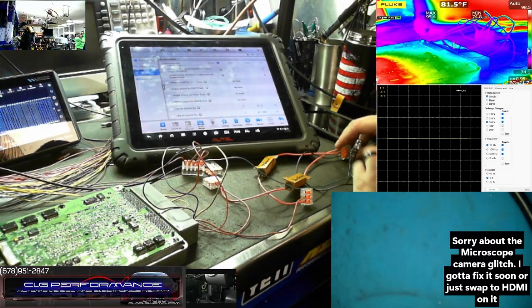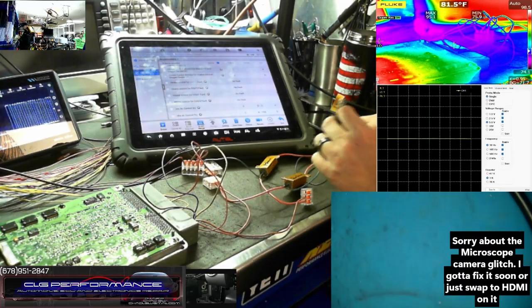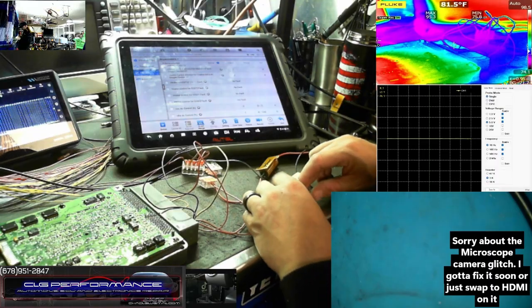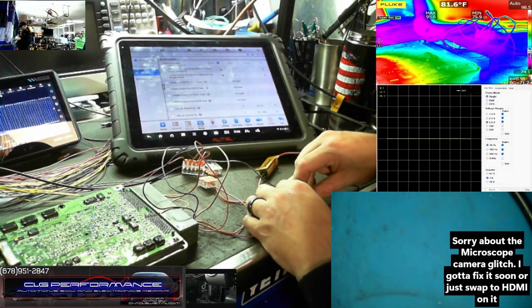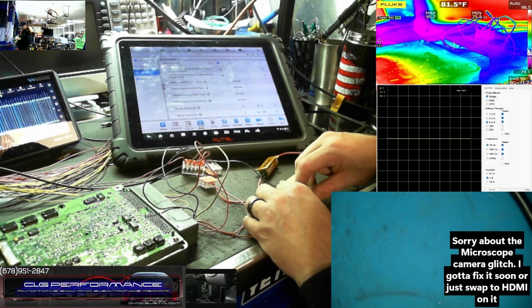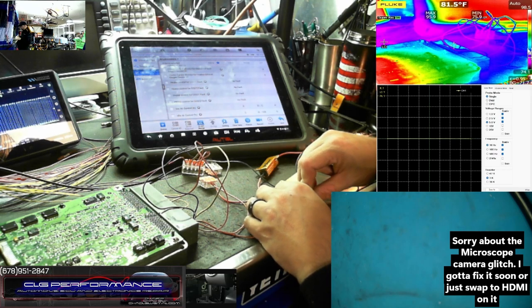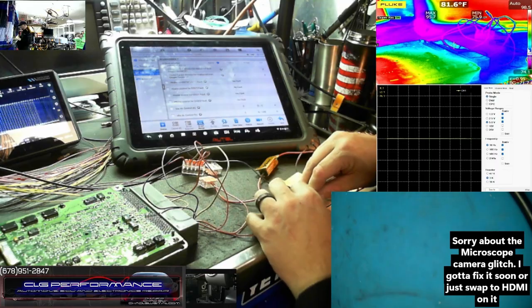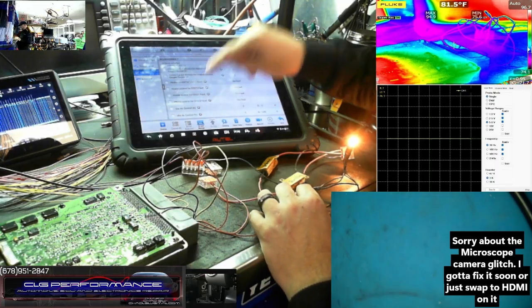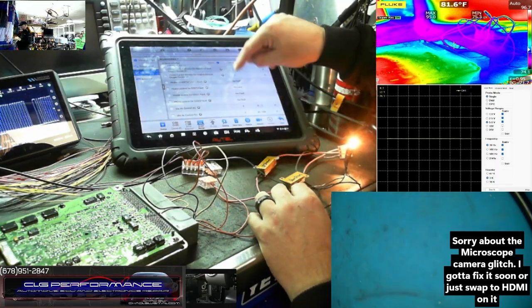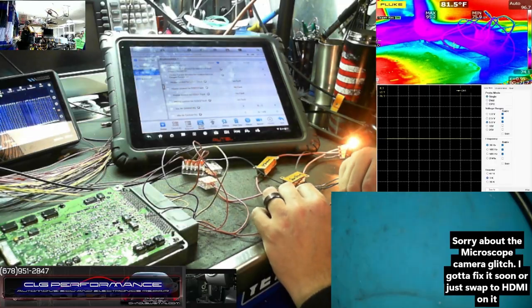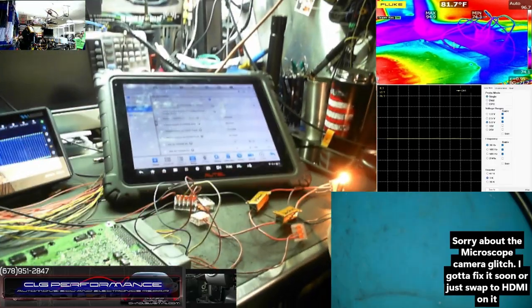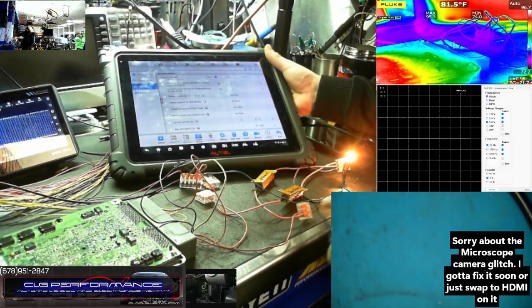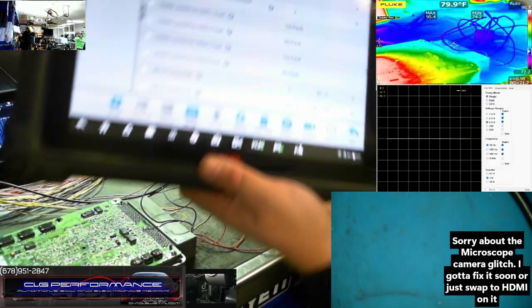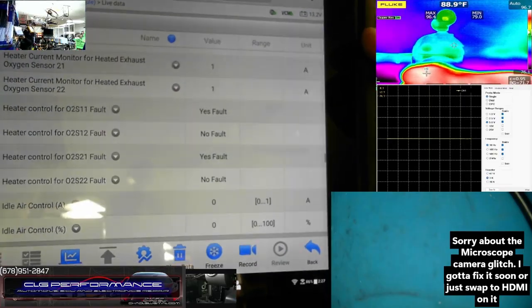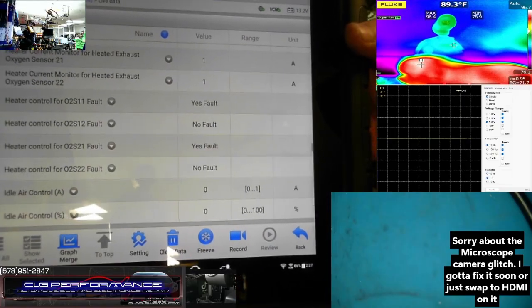Because I can interrupt. This will do upstream and downstream fault. This one will do an individual fault. Let's see. It may do 3 or 2 of them at least. Okay, yep. So the upstream, and that's what I'm hooked to, both upstreams just faulted. So as you can see, I just undid the upstream ones, and now it's only saying that upstream is faulted.